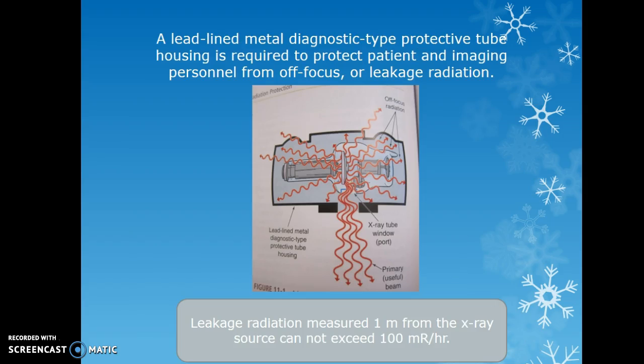Lead-lined metal diagnostic tube housing is required to protect the patient and imaging personnel from off-focus or leakage radiation. Leakage radiation comes from the tube in all directions, though most is focused out through the shutters via the collimator. Even with lead lining, some leakage occurs, and it cannot exceed 100 mR per hour measured one meter from the x-ray source. Engineers at hospitals can check this periodically.